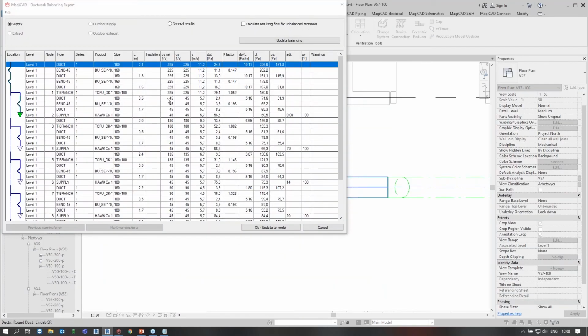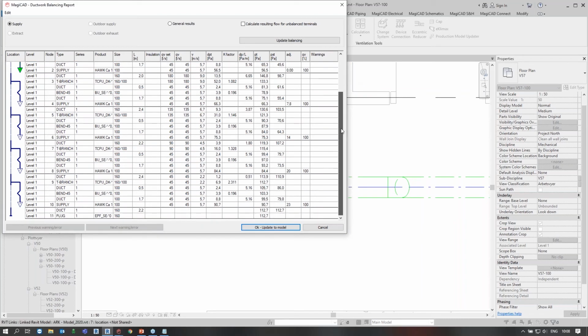Okay, so here we now see that at the start, we have 225 liters per second. In the main duct, I have a velocity of 11.2, which is a little bit too high. And the fan or air handling unit has to provide a pressure of 226.9 Pa.